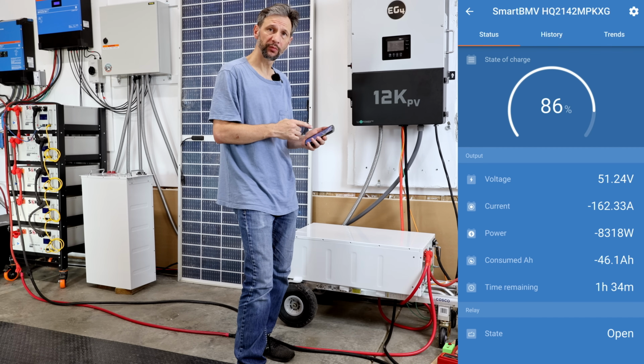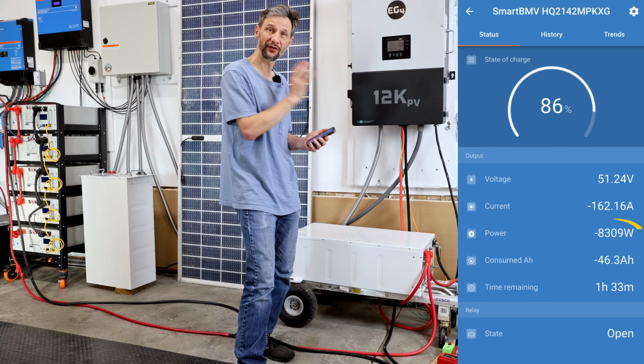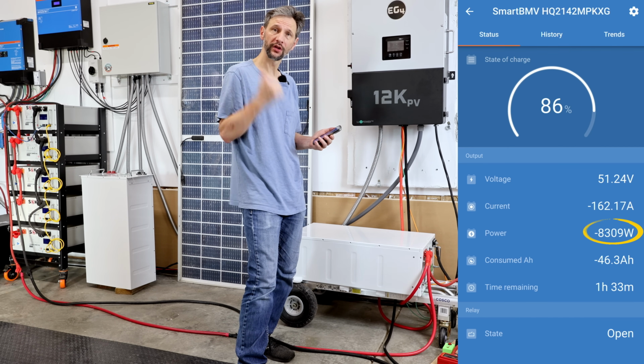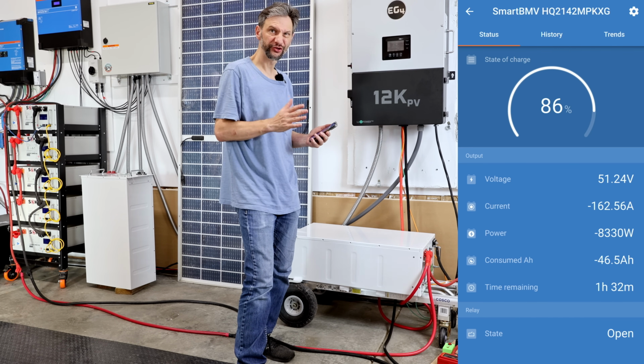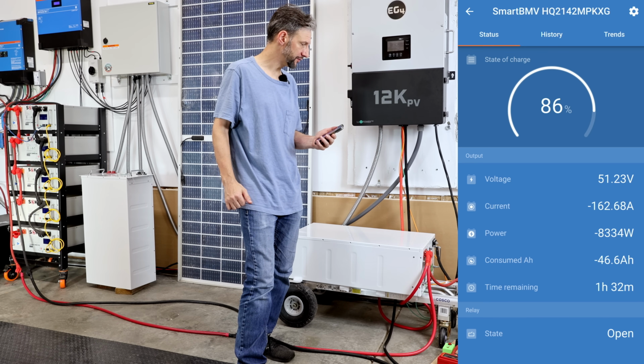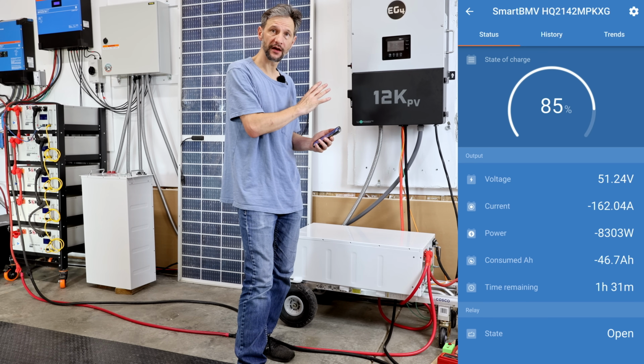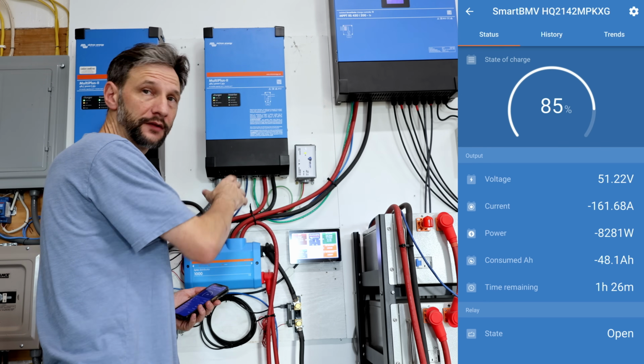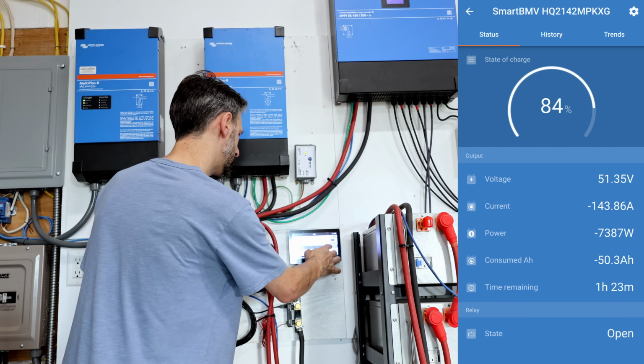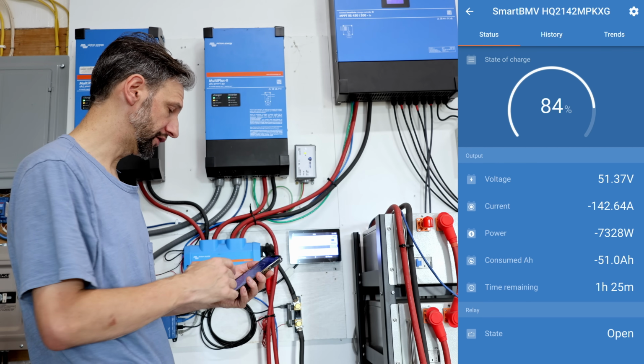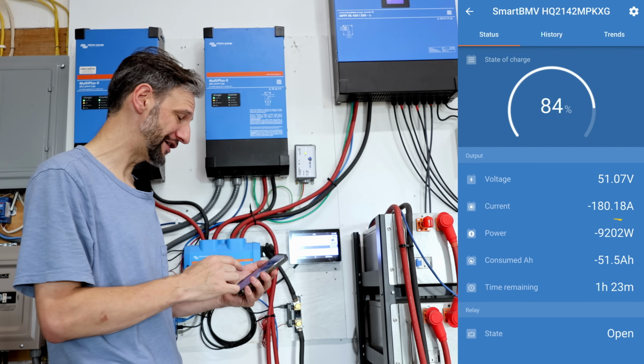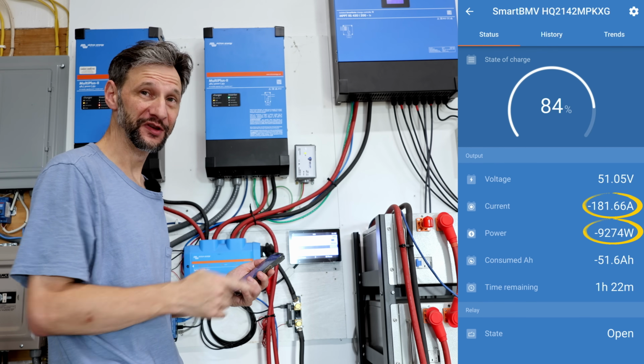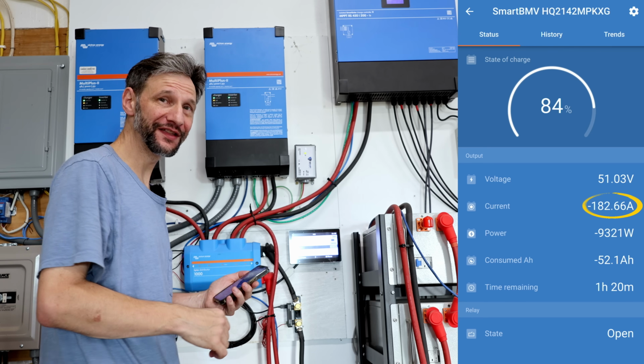All right, the EV's plugged in and I'm pushing a little over 8,000 watts that direction. Now, let's pull some from the Victron side. I'll filter it out a little bit, but you can hear the fans howling in the background here. That thing's pretty much maxed out. All right, now we'll start pulling from this side. Oops, went the wrong way. Pushed 1,000 watts instead of pulling it. All right, let's see. All right, there we are, 9,000 watts, 180 amps. BMS is still rolling. Let's go all the way to 10,000 watts.